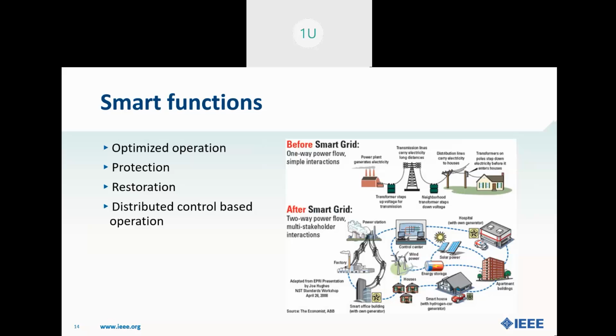What is the role of this power in a smart substation? Let me check. There will be a number of consumers under a substation. Sometimes they will be industries. When they use their machines, they consume a large amount of reactive power. If the substation is not equipped for this at its voltage level, then the voltage received by the secondary consumers will decrease. That is, a voltage dip occurs. If we have a smart substation, then the sensors in the smart substation sense that the company or industry needs a large amount of reactive power, and they will transmit it to the industry. This will decrease the chance of voltage sag.